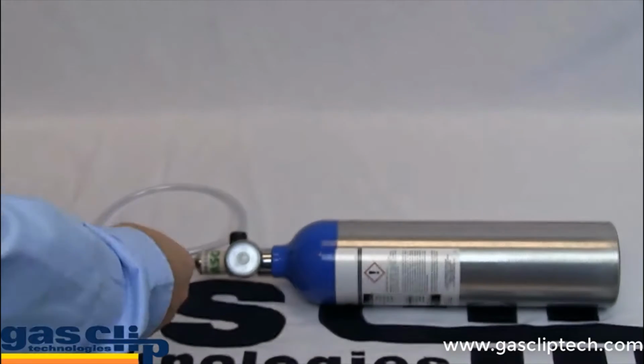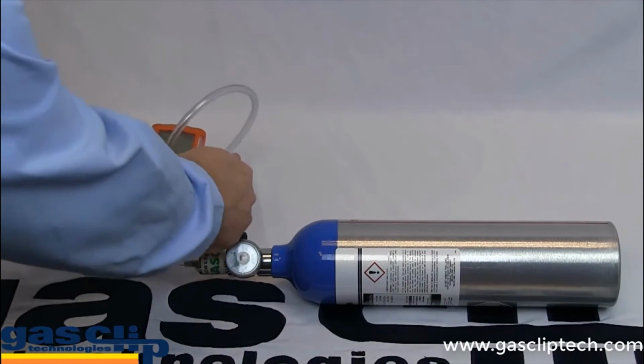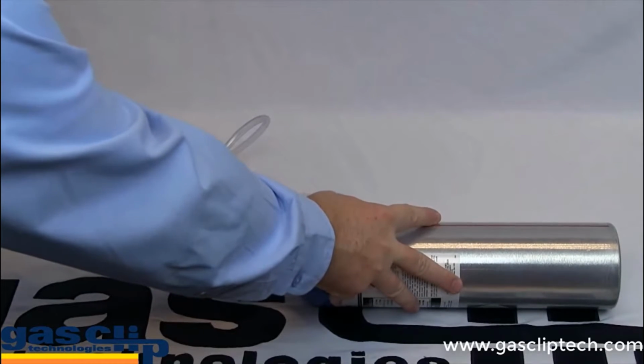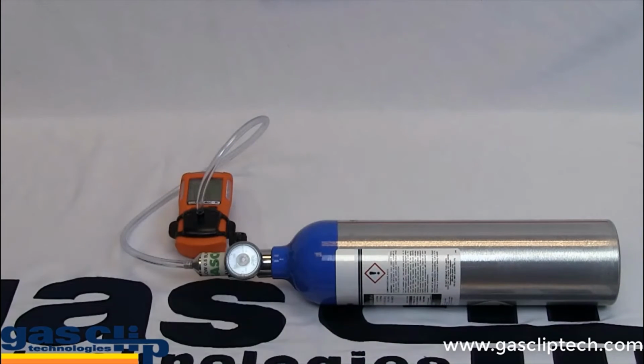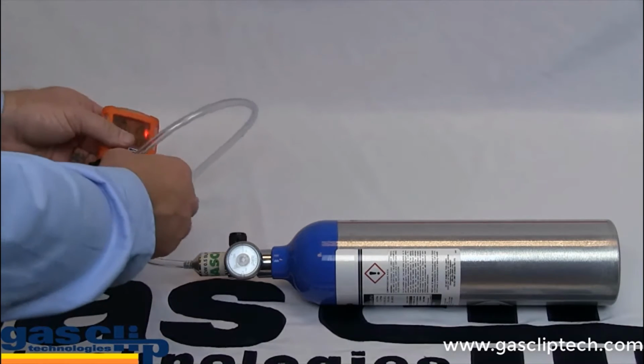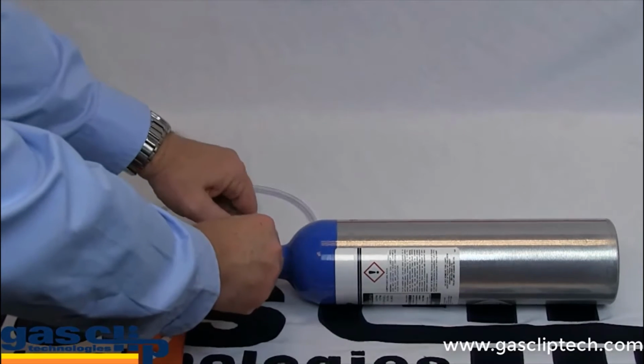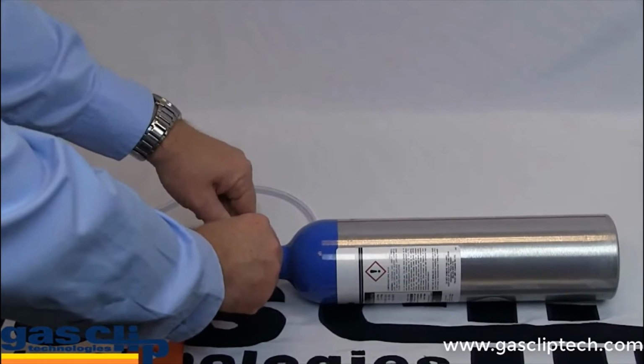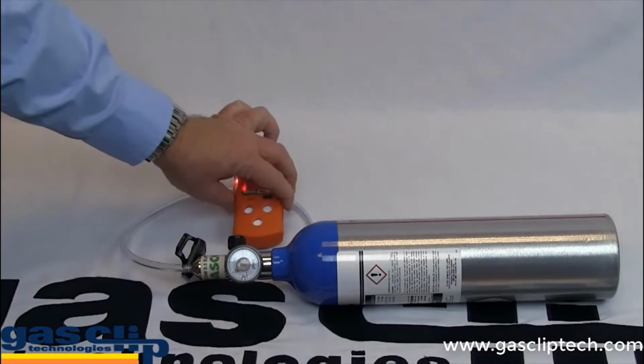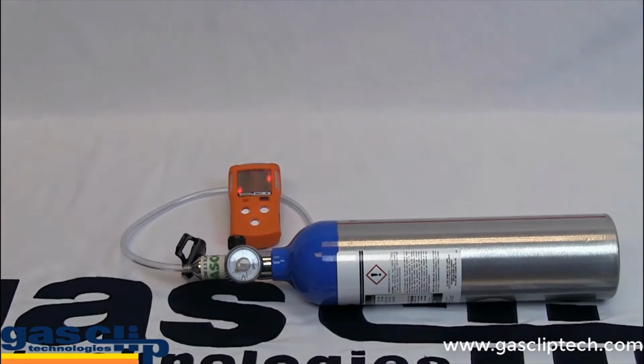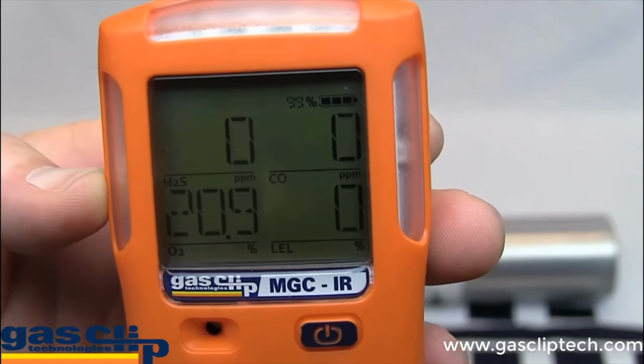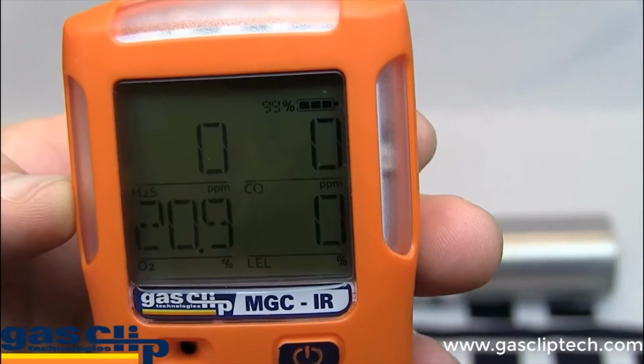At this point, attach the provided calibration cap and turn your regulator on. The monitor will now self-calibrate. This process takes approximately 1.5 minutes. Once the monitor is finished calibrating, it will go into alarm. Simply remove the calibration cap, turn your bottle of gas off, and set the monitor to the side, and it will adjust back down to 0, ready for use. Once the sensors have stabilized, the monitor has been successfully calibrated and is ready to use.